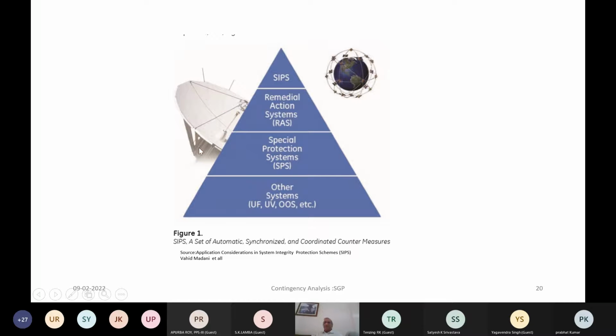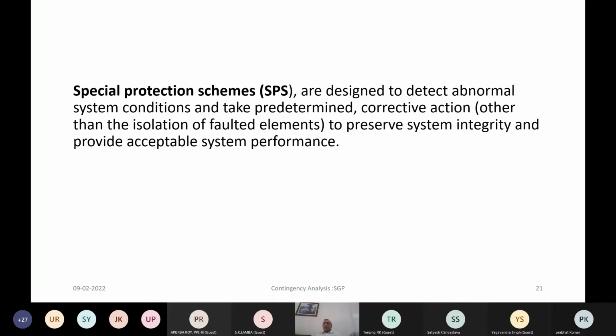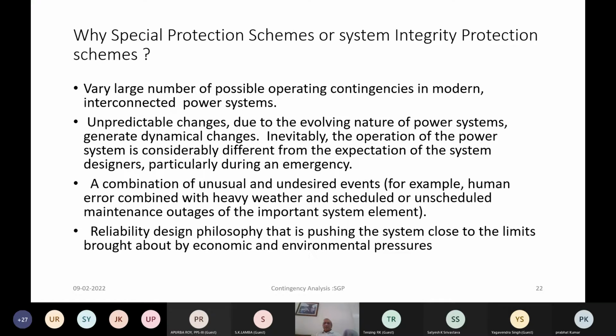That's why even the communication network is shown in this figure with the GPS support. So these are the sort of new technologies, and to do this, phasor measurement units, PMU, are being deployed in the power system at 400 kV level and 765 kV level. So special protection schemes, as I mentioned, are the schemes which are designed to take care of the system parameters within their normal limits and preserve the system integrity within the tolerable range of the parameters.